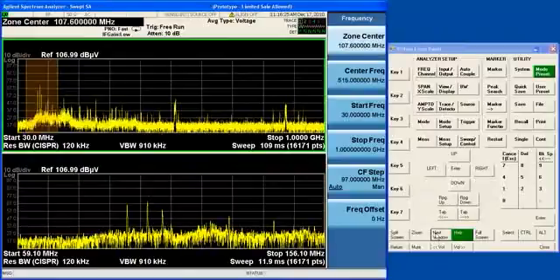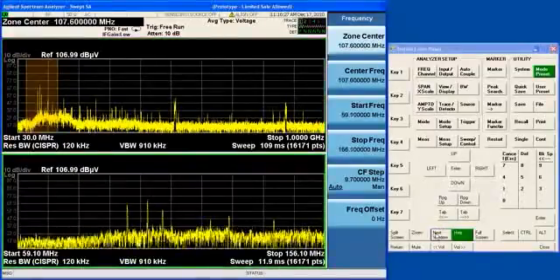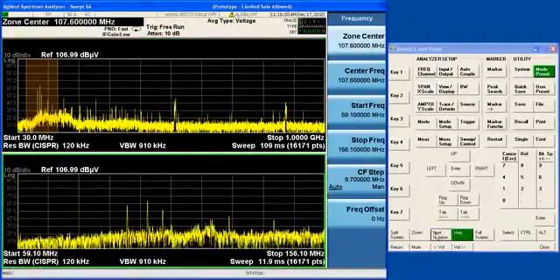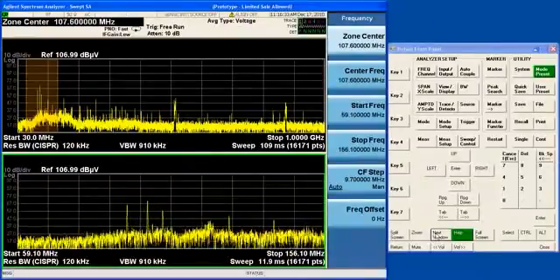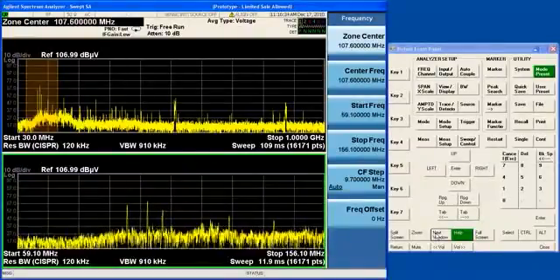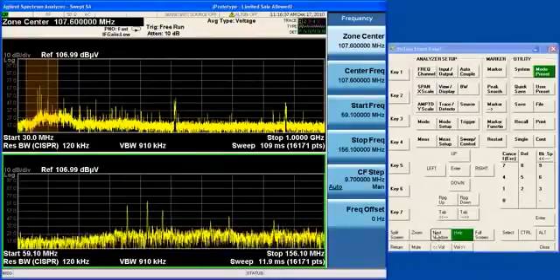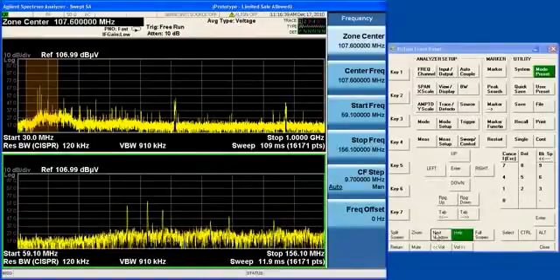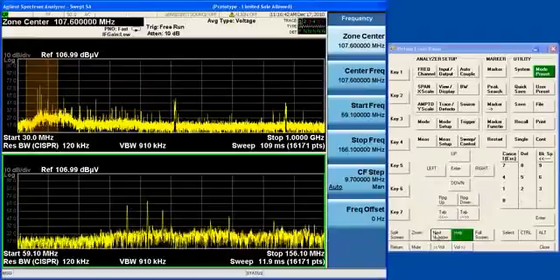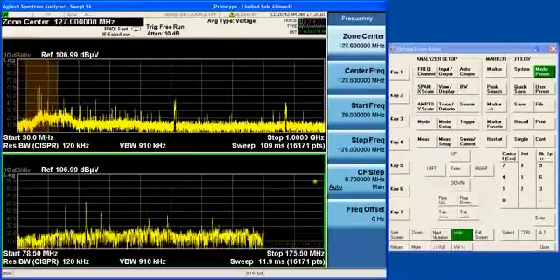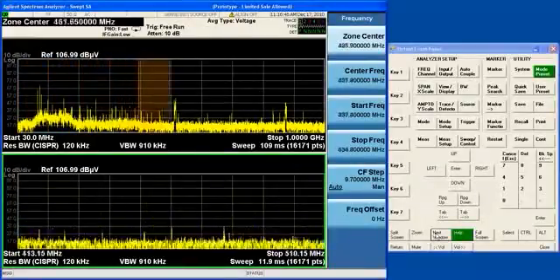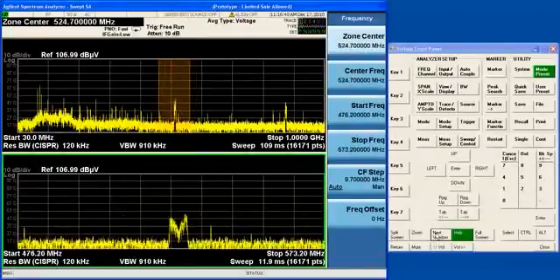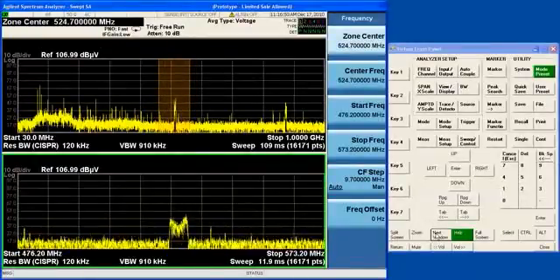Then the next window again, and the lower window is active, and it sweeps. So the basic principle for Zone Span is you take a sweep in the upper window of the full range of frequencies in which you are interested, and then you can move through them with the Zone region in the lower window, examining each one in more detail.